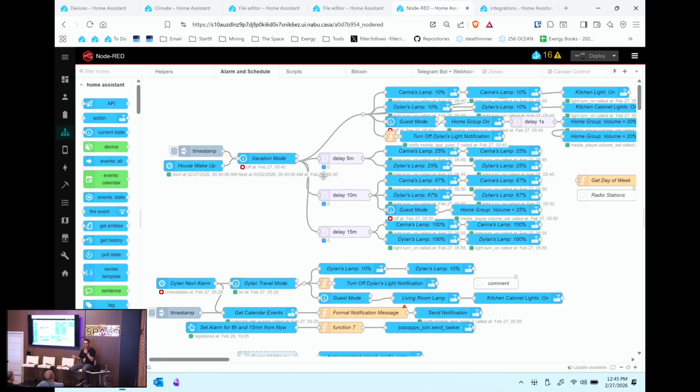And so if you wire it correctly, for example, the ones around the building, we have them wired such that the furnace is on stage 2. Stage 1 is not wired at all. But when that thermostat calls for stage 1 heat, it kicks a miner on and the blower fan and sucks the miner that's ducted in, sucks that heat all over it and pushes it around the building.